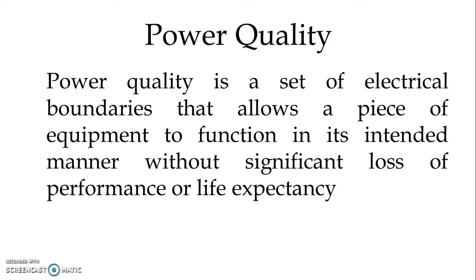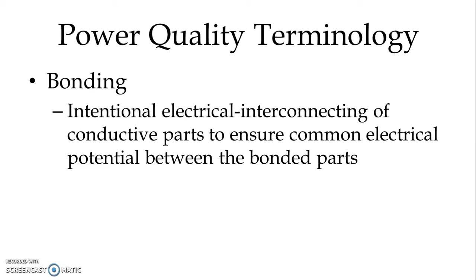Now let us study certain terminology associated with power quality. Bonding: intentional electrical interconnecting of conductive parts to ensure common electrical potential between the bonded parts. Normally, we do bonding with a very low resistance conducting part of two equipments to ensure both equipments are at a similar potential. That is why bonding is required.